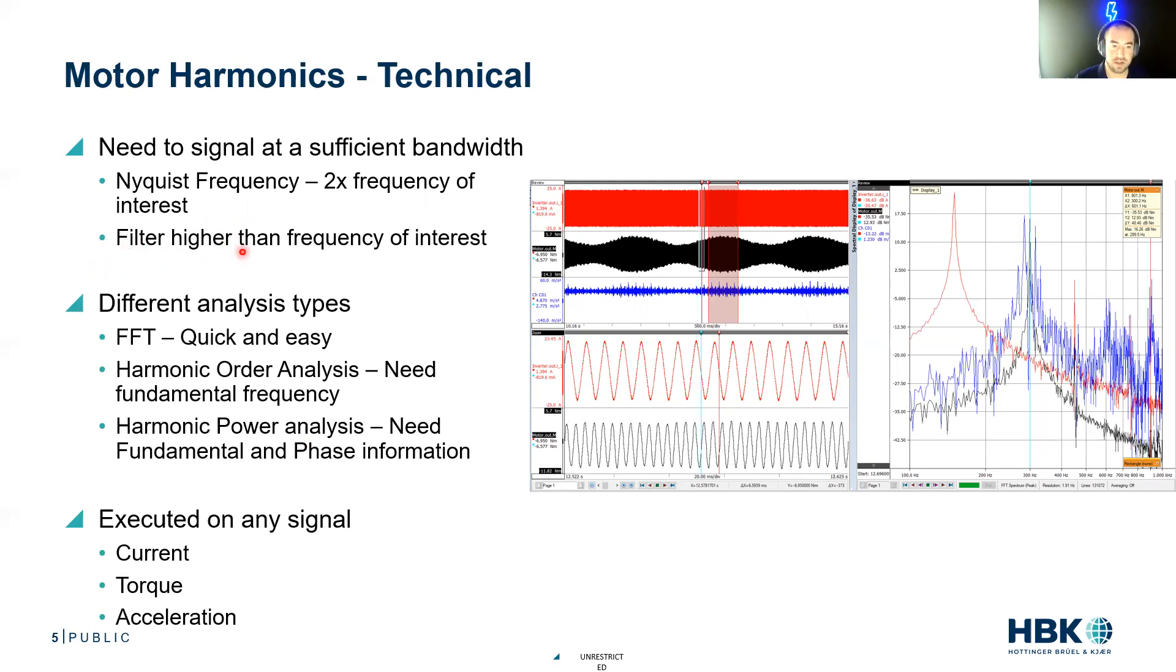And we want the frequency of interest to be within the filter constant of our frequency. So your instrument's going to have a filter on it. If your fifth harmonic is at 500 hertz, you probably want your filter to be at that 3 dB point of 600 hertz, which probably means you're sampling at something like six kilohertz or higher. Filter higher than the frequency of interest and sample much higher than the frequency of interest.